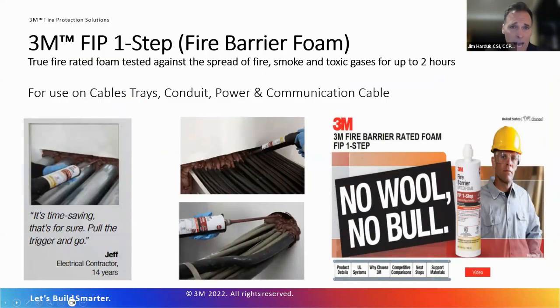So again, some of the applications for the FIP one-step foam. It's a great product to use on cable trays or anywhere where you have bundled cables. And again, because the material expands and increases in volume, we typically don't require any backing material behind it, so you don't need to use mineral wool or any type of backing material. Next slide.